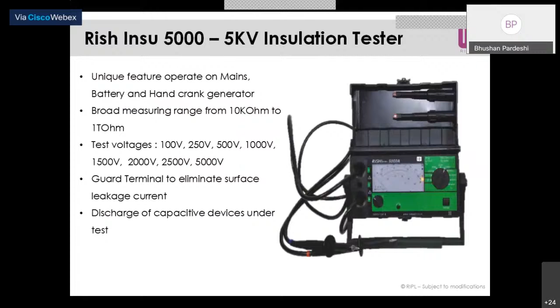So this is also another 5 kV insulation tester, but the previous one was the analog type. This is the digital insulation tester. Again, it has a test voltage from 500 volt to 5000 volts with resistance measurement up to 1 tera ohm. It comes with diagnostic features incorporated in this instrument, that is automatic polarization index and dielectric absorption ratio. And again, this operates on battery and mains.